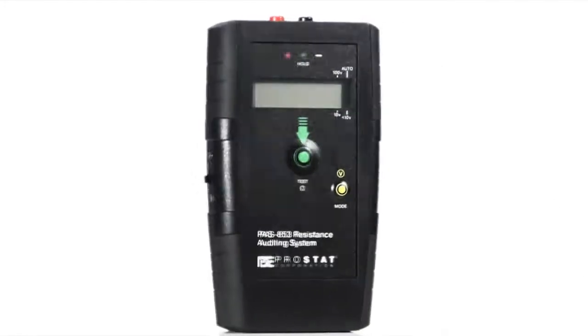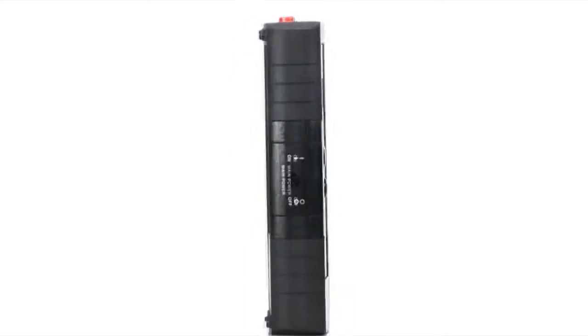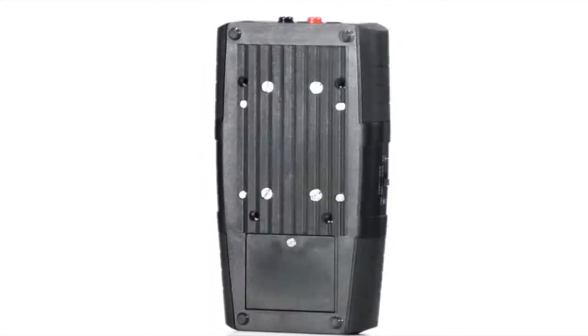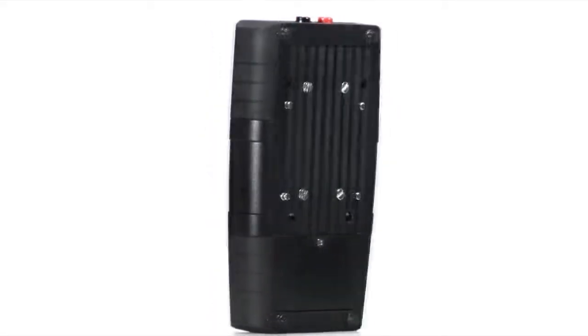The PRS-853 is our answer to a low-cost, constant voltage version of the PROSTAT PRS 801 resistance system. While not intended as a laboratory-level instrument with the range of the 801, the PRS-853 is virtually as accurate in its own operating range. The 853 is designed for routine plant audits and it's very easy to use.